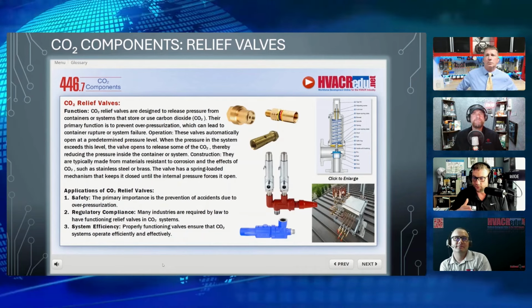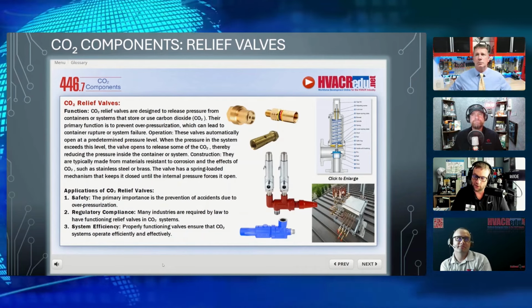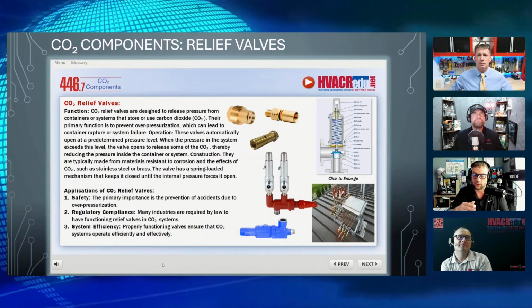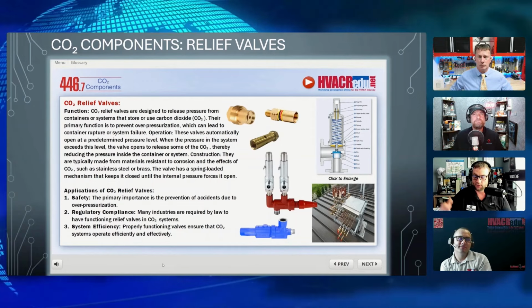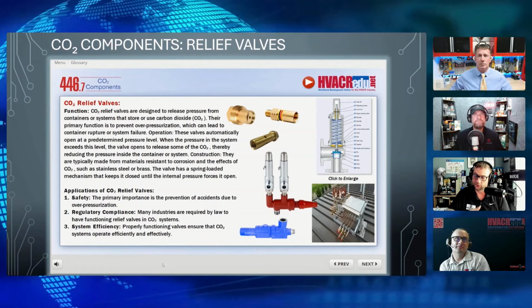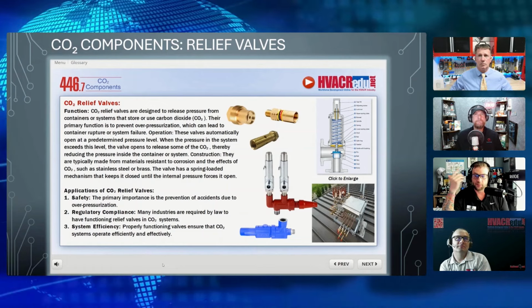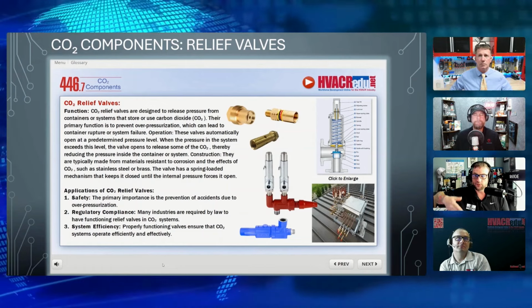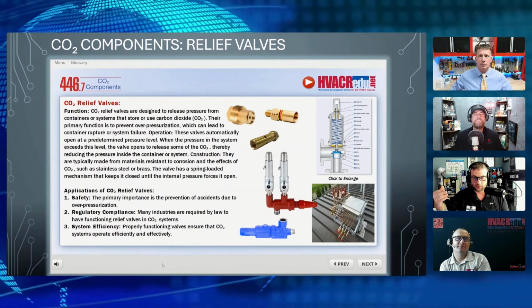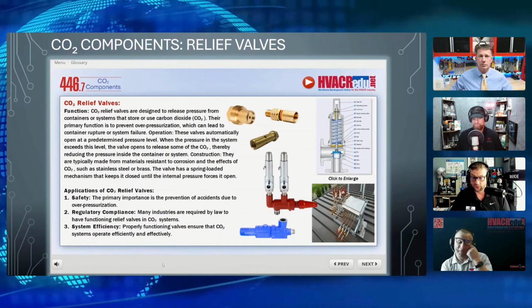So if you were to be on a system and it went into a high pressure event where it just shut down before it actually hit the relief, and then you're like, oh, there's a problem with the compressor. You isolate the compressor and maybe you forgot about the crankcase heater. It's going to keep continuing to heat up that refrigerant, and what's going to happen?